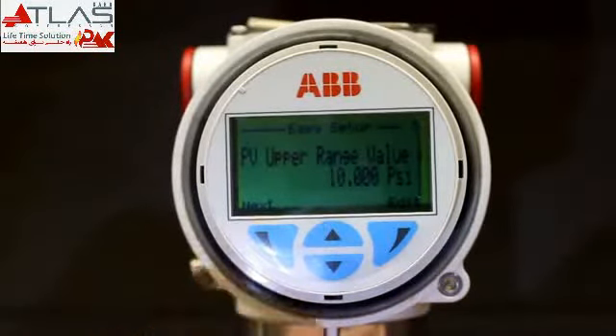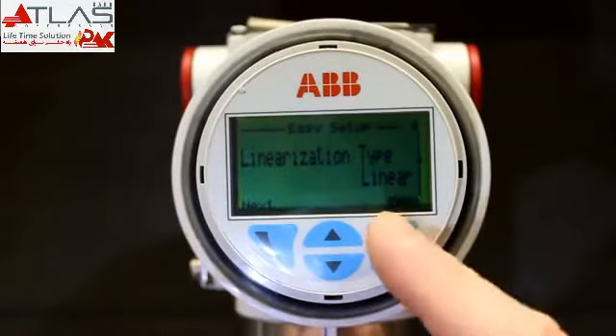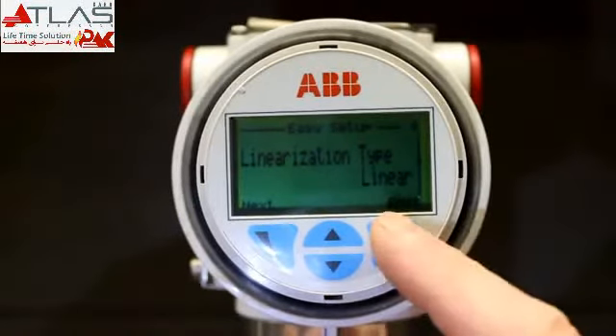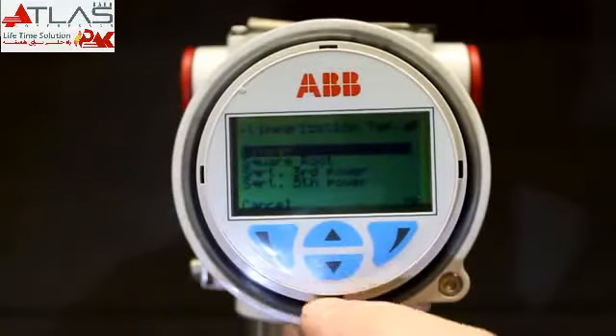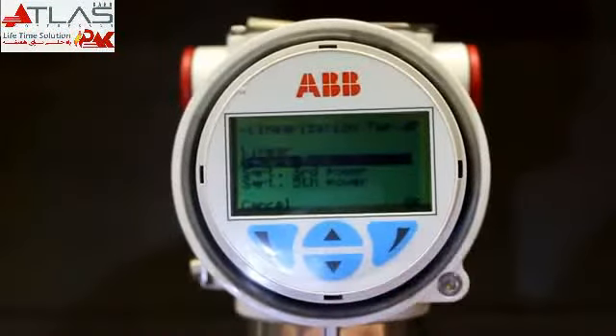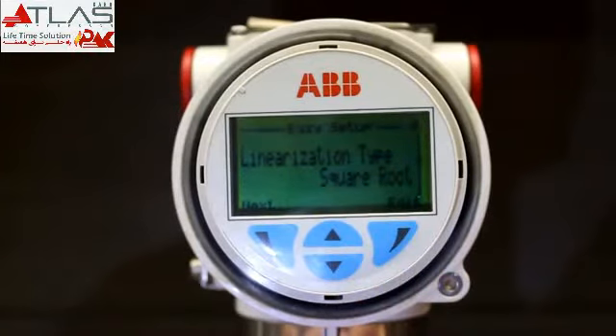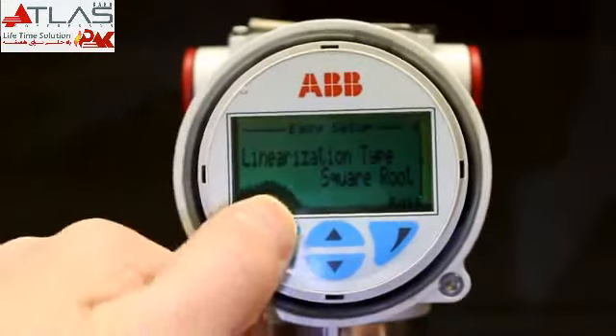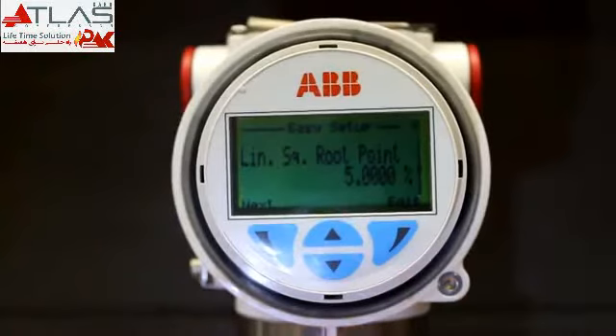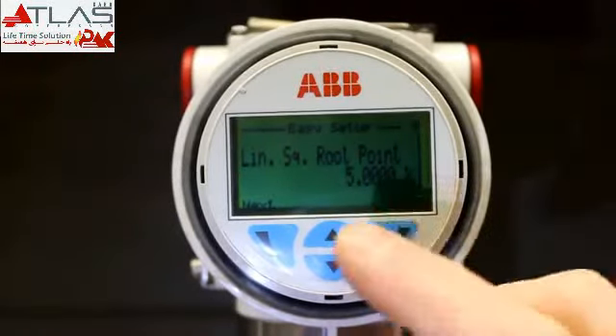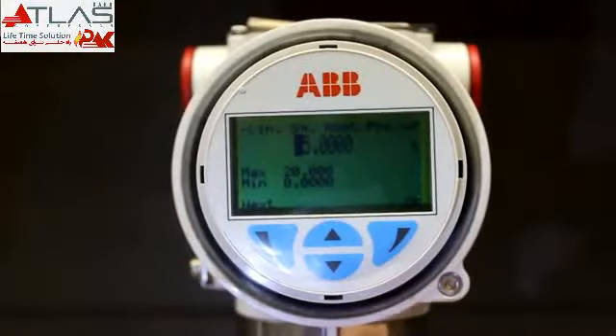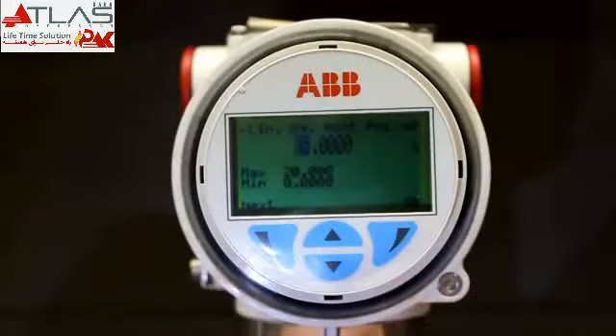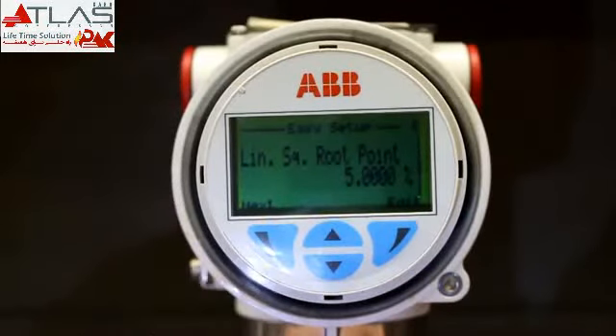The next one is linearization type. To change that, you hit edit again, and most of these functions are changed the same way. You've got linear, and we change it to square root, hit OK. Linearization type is now square root. We'll hit next again to the next function: the linear to square root transition point. You can turn it down to 0%, or bring it up as high as 20%. Right now it's at 5%. We're not going to change that, so we'll hit OK and go to next.